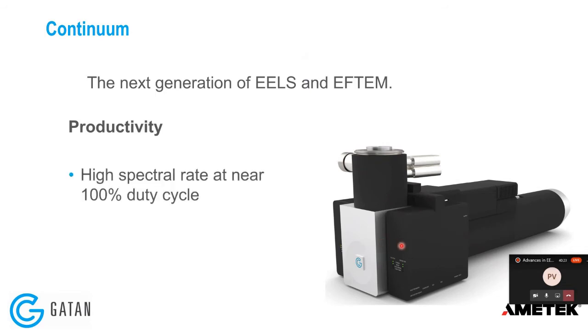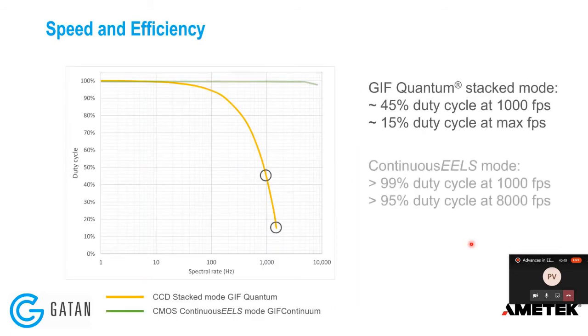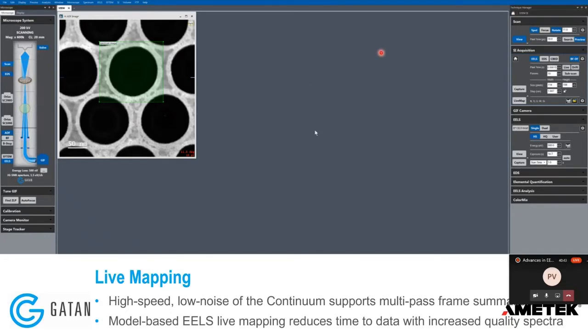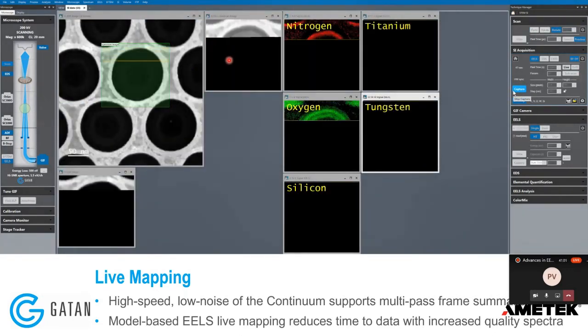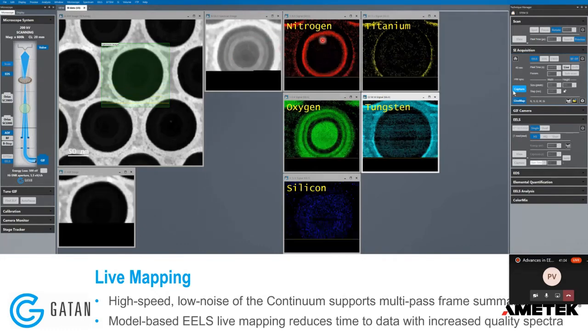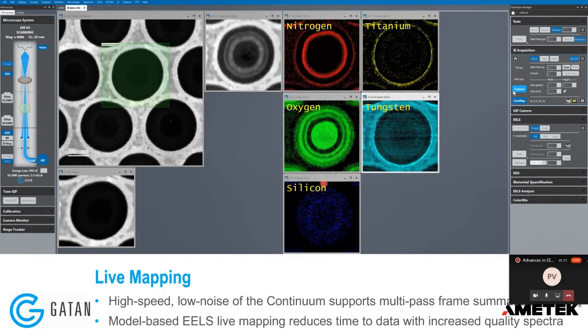The continuum camera is much faster and easy to use, with quite a lot of workflows covered in recent webinars. A major new feature introduced is live mapping. You scan the beam over the area of interest, select the elements, click live map and capture, and tell the software how often to scan the area. The software automatically generates elemental maps — for example, nitrogen, titanium, oxygen, tungsten, and silicon — and you can go back to the same area to improve map quality. This was done with a 3000 eV energy range.